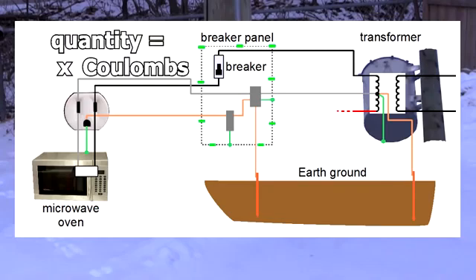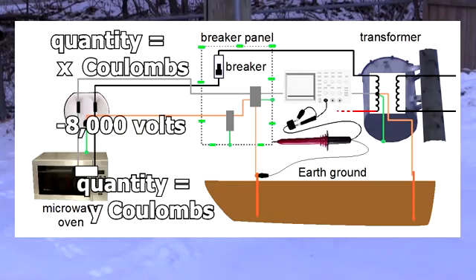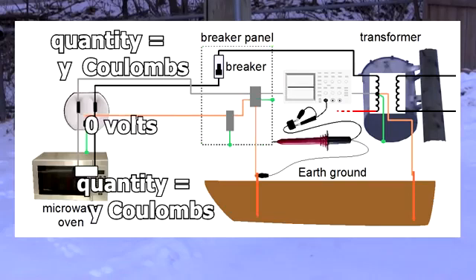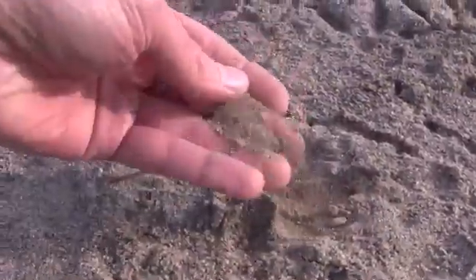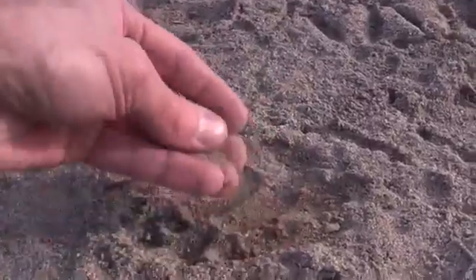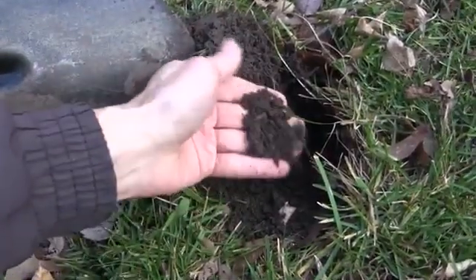And yet another way to look at it is that the negatively charged case has a certain quantity of charge, and the neutrally charged ground has a different quantity of charge. That means they have different electric potentials — a potential difference, or a voltage, exists between them. Since there's voltage between them, if you connect them with a wire, current will flow. Electrons will flow from the negatively charged case to the neutral ground. For a ground rod to work well, the ground does have to be electrically conductive, meaning it has a low resistance. Dry sand like this is not very conductive and is a bad ground. But moist soil is fairly conductive and is a better ground.